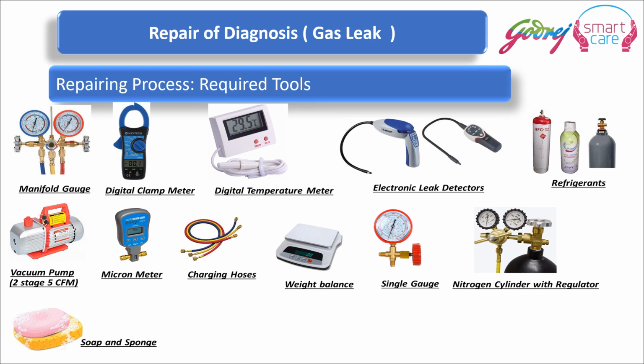Required tools are a manifold gauge, digital clamp meter, digital temperature meter, electronic leak detector, refrigerants, a 2-stage 5 CFM vacuum pump, micron gauge, charging hose, weighing machine, single gauge, nitrogen cylinder with regulator, and soap and sponge.